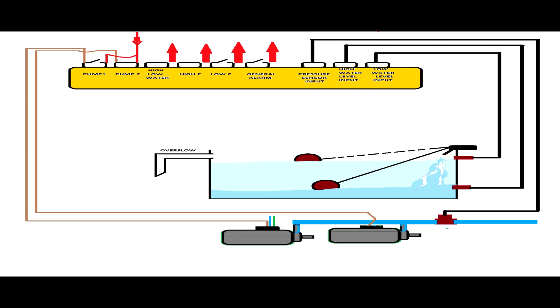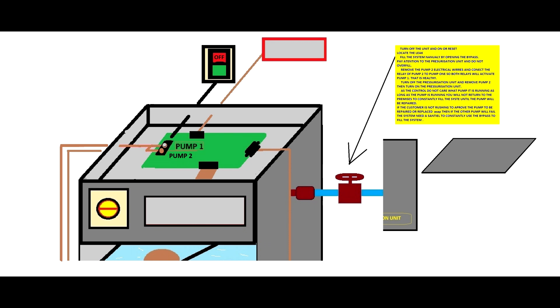So if we pull out the pump number two and we will connect in parallel the relay number one and relay number two, the relay number two will drive pump number one as much as the relay number one will drive pump number one. It's a parallel connection because the printed circuit board does not know which pump is running. It just needs to be a pump.